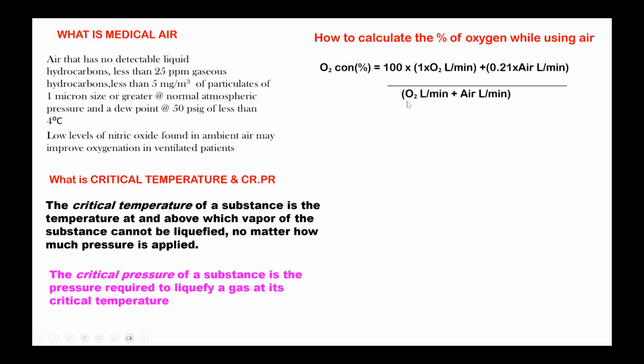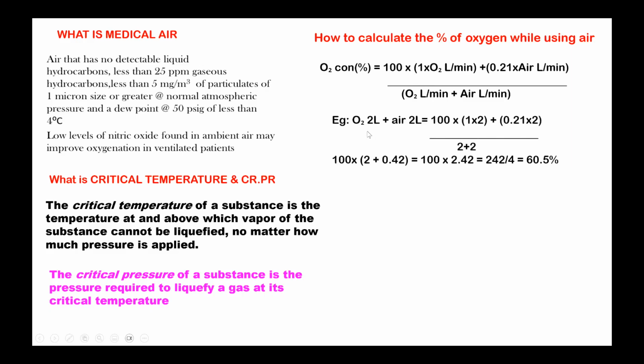The formula is this for oxygen concentration; you have to use it. For example, if you are using 2 liters of oxygen and 2 liters of air, then you multiply. Pure oxygen is 100% oxygen, so you get 100 into 2, whereas air contains only 21%, or 0.21, oxygen, and you are also using 2 liters of that, with a total volume of 4 liters. Multiply all these things and you get roughly 60.5% oxygen delivered when using 2 plus 2 of oxygen and air.